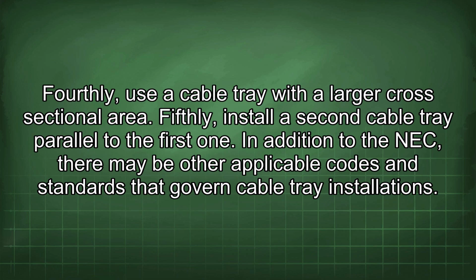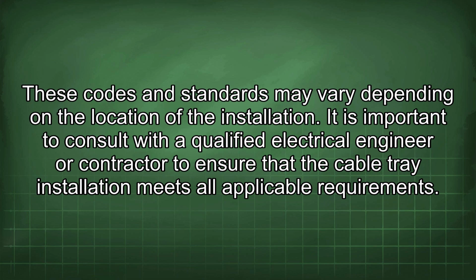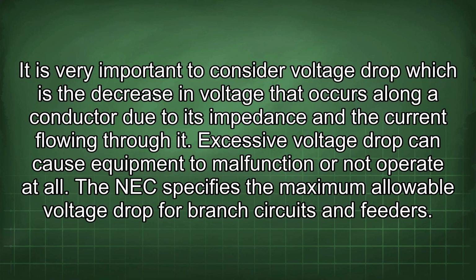In addition to the NEC, there may be other applicable codes and standards that govern cable tray installations. These codes and standards may vary depending on the location of the installation. It is important to consult with a qualified electrical engineer or contractor to ensure that the cable tray installation meets all applicable requirements. It is very important to consider voltage drop, which is the decrease in voltage that occurs along a conductor due to its impedance and the current flowing through it. Excessive voltage drop can cause equipment to malfunction or not operate at all.